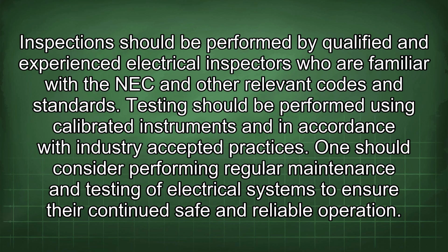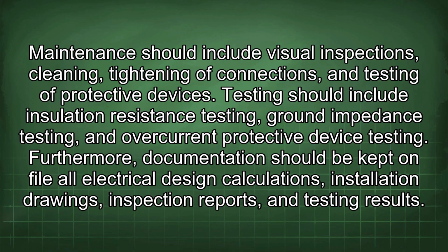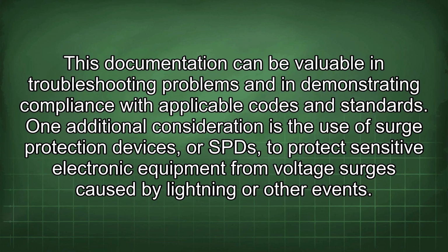One should consider performing regular maintenance and testing of electrical systems to ensure their continued safe and reliable operation. Maintenance should include visual inspections, cleaning, tightening of connections, and testing of protective devices. Testing should include insulation resistance testing, ground impedance testing, and overcurrent protective device testing. Furthermore, documentation should be kept on file: all electrical design calculations, installation drawings, inspection reports, and testing results. This documentation can be valuable in troubleshooting problems and in demonstrating compliance with applicable codes and standards.